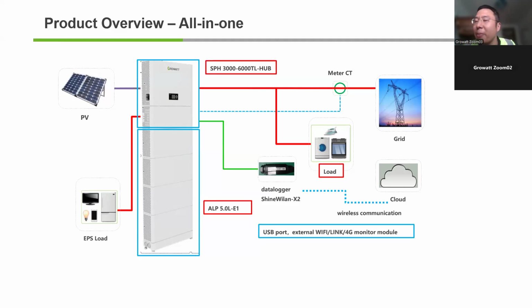It's not a battery. It has an inbuilt DC isolator between the inverter and the low voltage batteries. And secondly, it has an inbuilt smart meter. As long as this all-in-one is installed within 10 meters of the main switch, there's no need to install a smart meter at the main switch anymore.